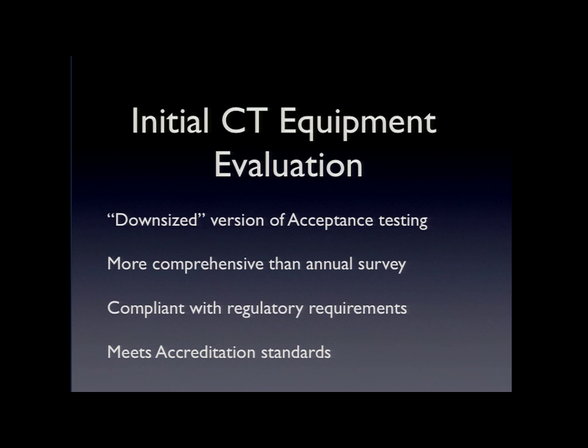Acceptance testing can be quite time-consuming and complicated at times too, and everybody wants their scanner as soon as possible. There's also the initial CT equipment evaluation, which may be a downsized version of the ideal acceptance testing.